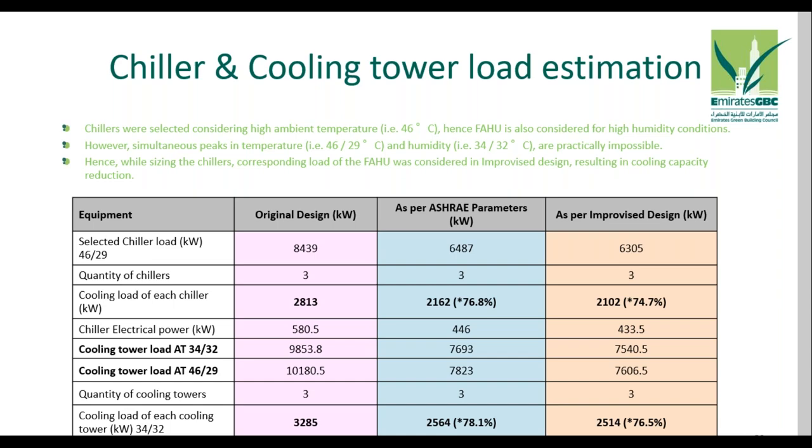That can be analyzed. What is the peak load at 34-32? What is the peak load at 46-29? And we can apply the same approach. So if we are selecting the cooling tower at 46-29, we can apply the in and out temperature for the cooling tower, and instead of 3 degrees, we can have an approach of 4 degrees to be on the safer side.